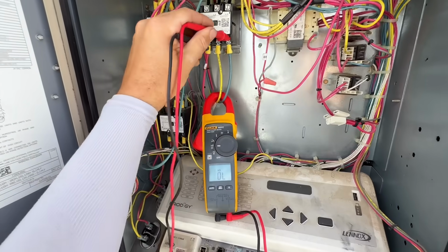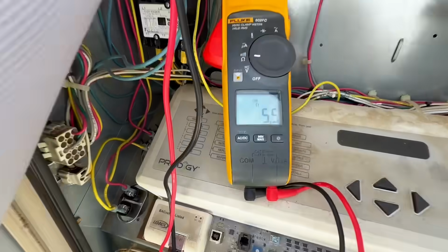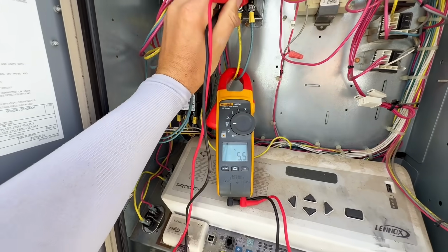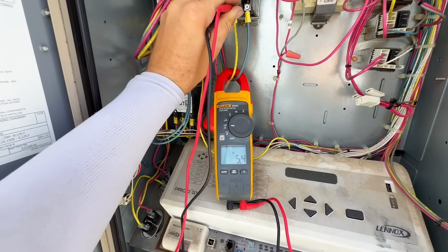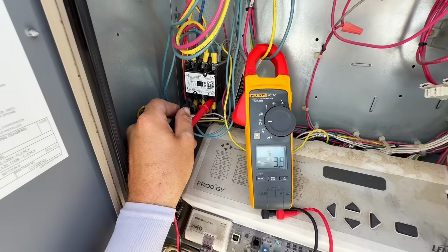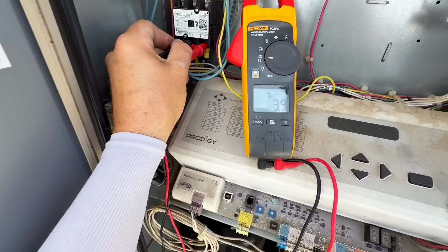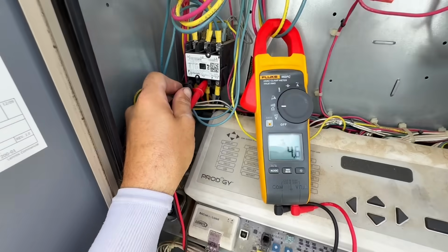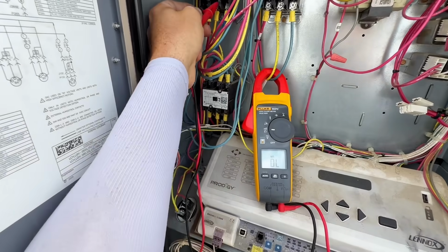And since we have a 3-phase blower motor and 3-phase compressor and stuff like that, all of the resistance readings on the components should be reading the same. Here, this is our indoor blower motor, which seems to be checking out so far. 1 compressor. Okay, let's check from here to here. Okay, that looks pretty good. Alrighty, let's go to our last compressor.